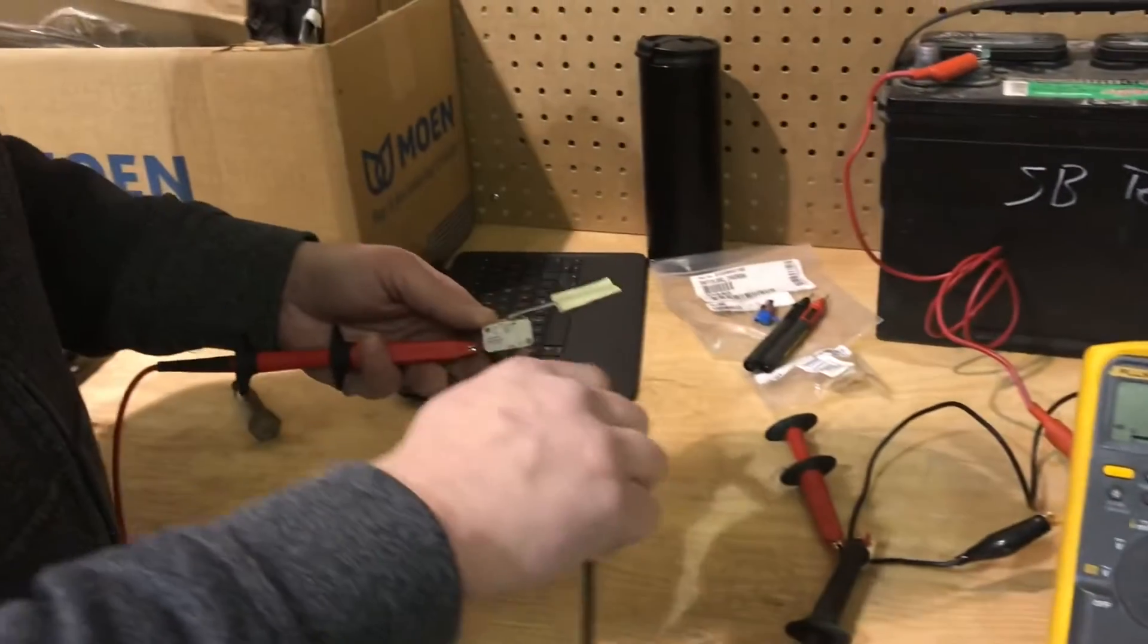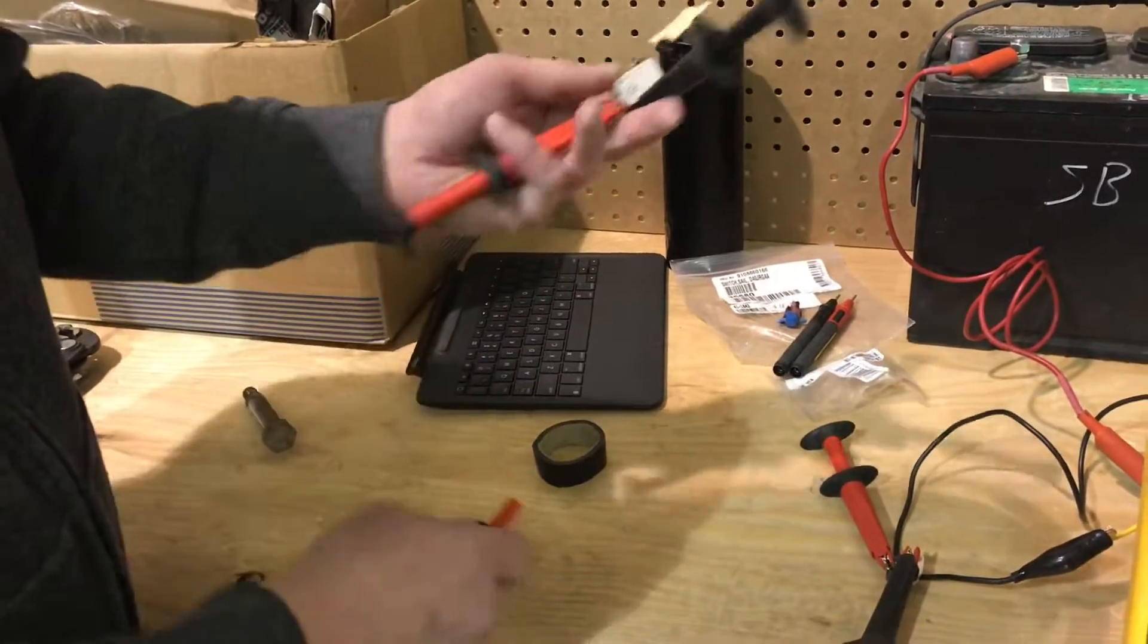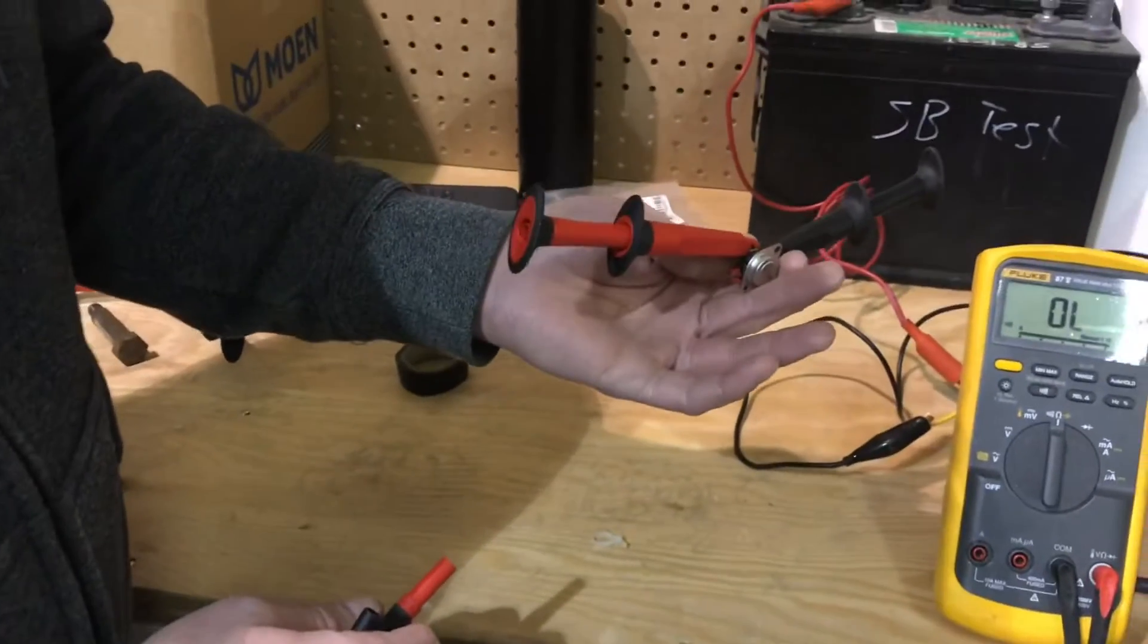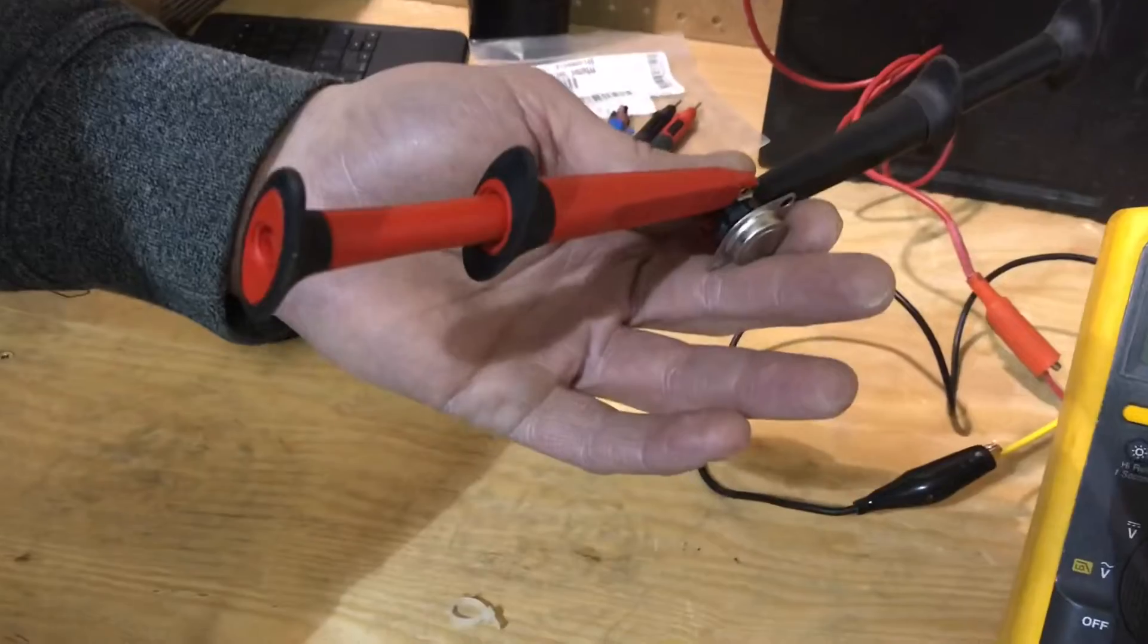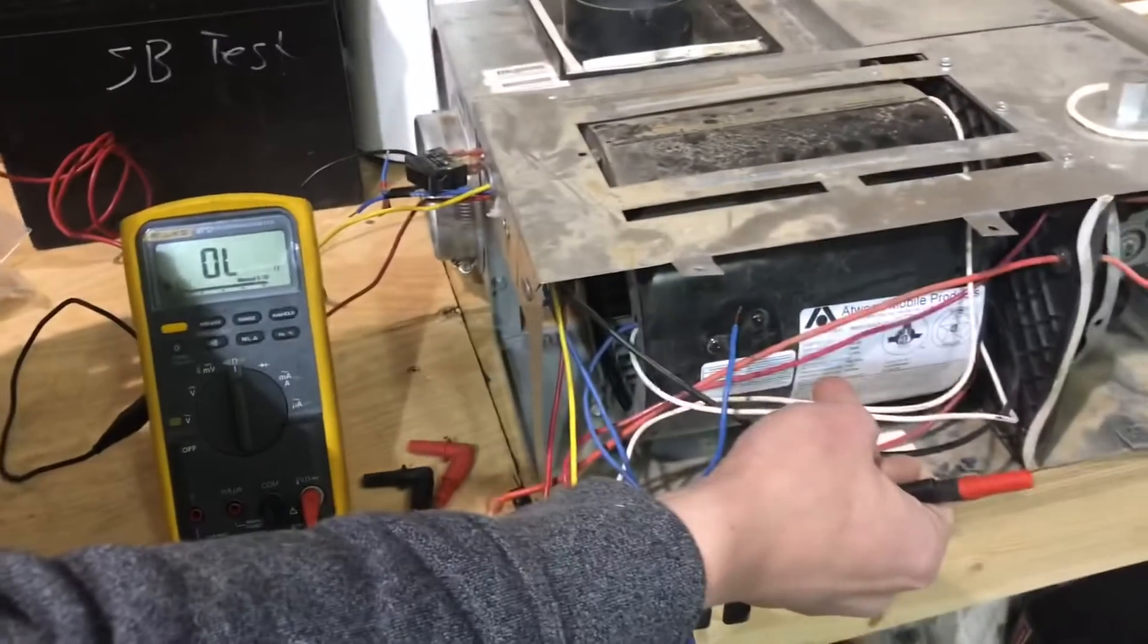Then you're going to come over here to this high limit switch. If you're testing it on the Atwoods, it's way at the back. Testing it, you have to either cut the wires or have these little pokies that can penetrate the wire insulation to test it.